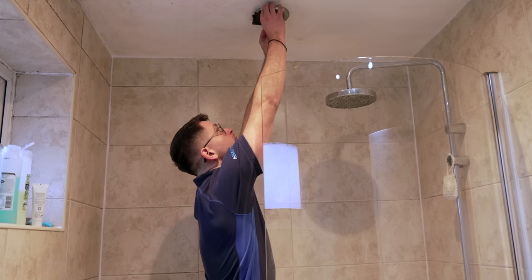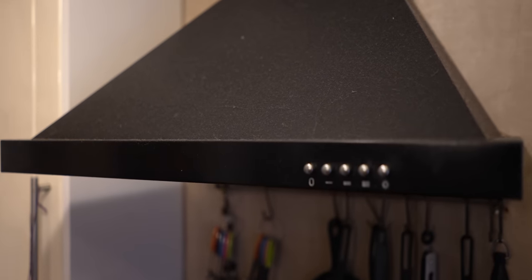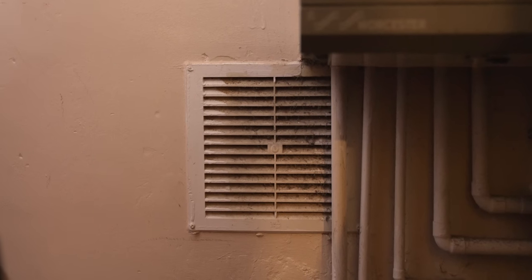If you do seal your house up, one thing I'm thinking of is condensation and no fresh air coming in. In the summer it's not really a problem — you can have a window open. But in the winter, does that not have a negative effect on the house? It's a really good point. What we're measuring with the air permeability test is uncontrolled ventilation that you might not know about at all. Things like extractors — we actually tape them up for the test. Normally trickle vents on windows, extractor fans, vents for boilers — you don't seal those up.